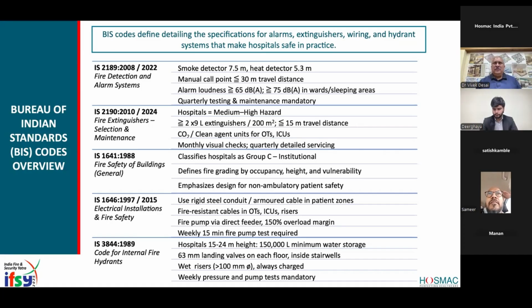Got that. So, guys, this is important to understand because wiring is one of the most extensively used materials in hospitals, and people tend to save cost here. So you should make that balance of where to stop cutting cost and where to be serious. I would suggest no compromise in critical care areas, or wherever you have electrical overload kind of areas, go for wiring which is safe. What happens, sir, when wiring gets burned, it generates more smoke and more carbon dioxide. Right. That is taken care of by using fire retardant and low smoke cables.